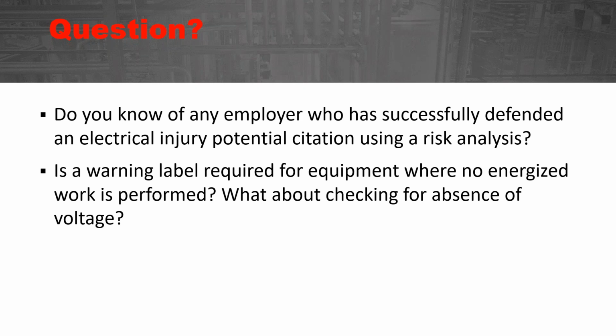But is a warning label required where no energized work is permitted? Well, all right, energized work is not permitted. If you're going to go in though, how are you going to know that it is electrically safe? Well, you've got to be suited up if you're going to open that equipment up and test for the absence of voltage, or use a Grace Safe Test Point on the outside of the enclosure. It almost sounds like I'm working for Grace. I like this product tremendously because it is a safety device. It can be a lifesaver.